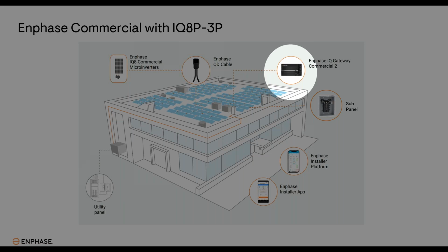For site intelligence, the microinverters communicate with the commercial gateway located at or near the PV subpanel. The inverters and gateway communicate via power line communications. The gateway gathers a lot of details about the PV system, monitoring DC volts, DC amps, AC voltage, AC output amps, AC grid frequency, and inverter temperature.